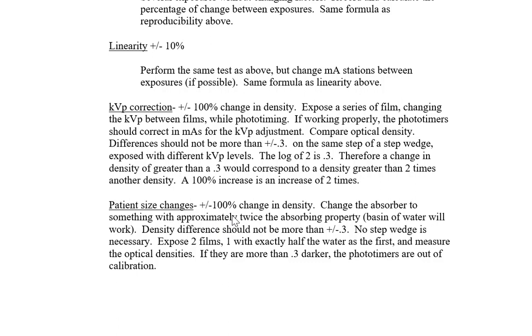If you make an exposure on a patient, and let's say the patient moved a little bit, and you have to reshoot, and you've got the same patient, and the size hasn't changed, what you're going to see in a lot of cases is that whenever the machine shoots, there's going to be a difference in the mAs. It almost never is going to shoot with exactly the same mAs. So because of that, there's a lenient variance for KVP correction, patient size changes in phototiming.